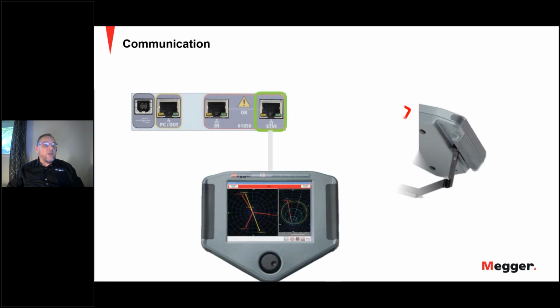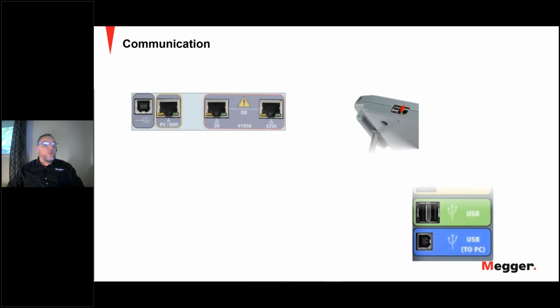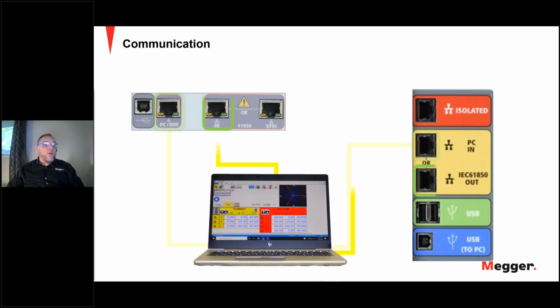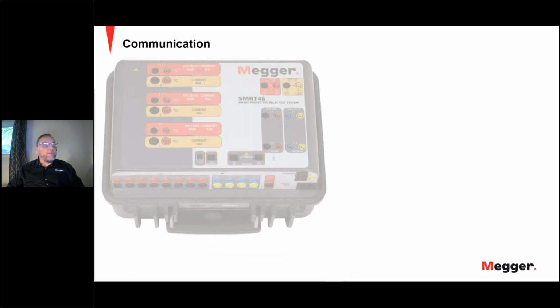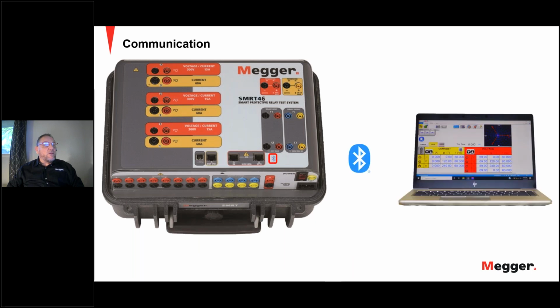Units also have an Ethernet connection for a PC and one isolated Ethernet port for testing on IEC 61850 systems. The USB port is also a connection to a PC, and it provides another form of control to the unit. A third option is an optional Bluetooth adapter that is provided with certain units to allow for wireless control using a PC.